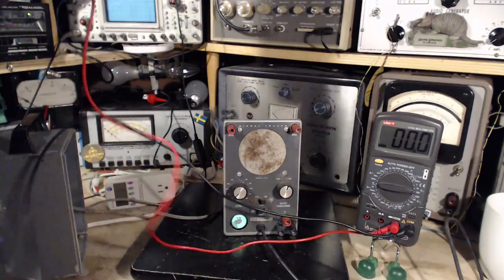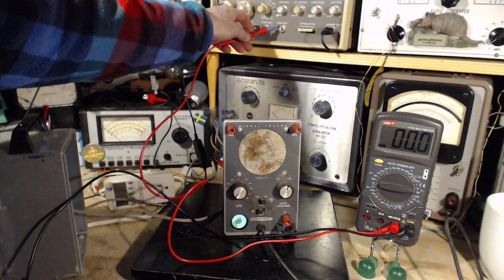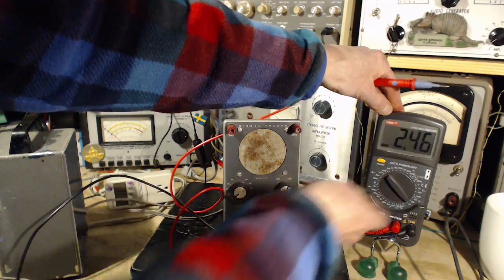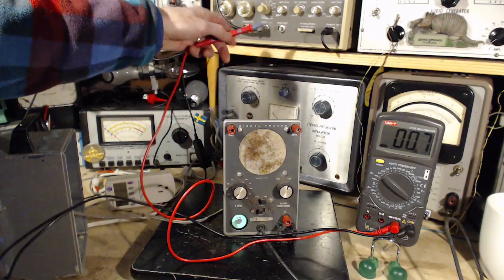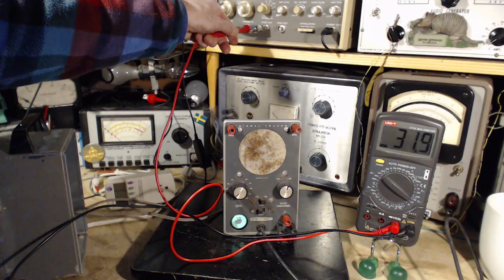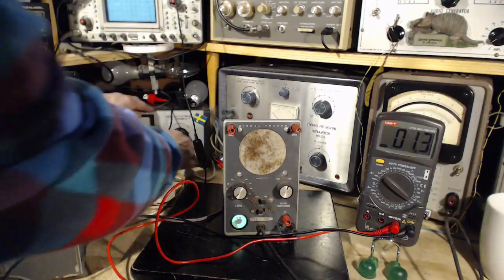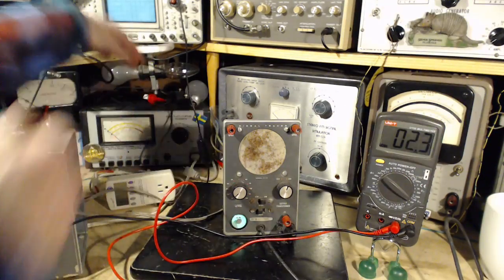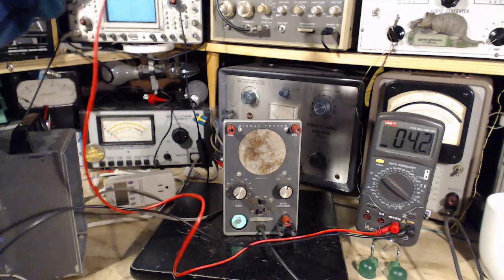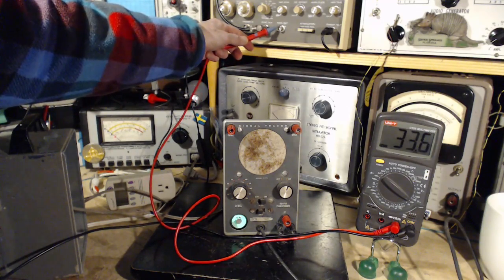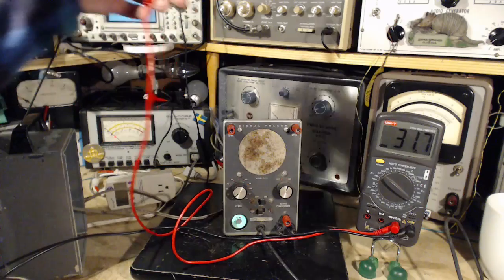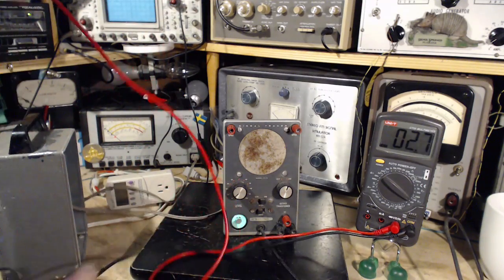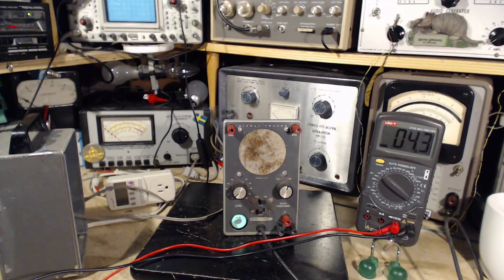Okay, so from ground to ground, any ground, this ground. DC. 20 volts. Let's put it to 200. 200. Here we go. 30. Okay, I'm going to switch the plug around. Touch the probe. And what do we get now? 30. Same voltage. So that voltage is probably a leaking over voltage through a capacitive connection, or very high resistance connection, maybe through weak insulation, transformer insulation, something like that.